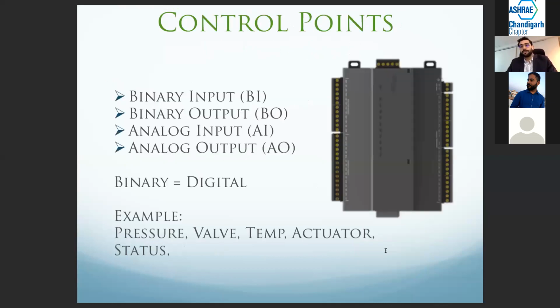We will go over some basic control points. On a controller, at the end of the day, a point is either an output or an input, and it is either binary or analog. So we have binary input, binary output, analog input, and analog output. Binary is 0 and 1, so it's on or off, and analog is a modulating signal. Let's do a couple of examples. Take temperature. A temperature reading can fluctuate, going up or down by decimal points, so at the end of the day that's an analog signal.